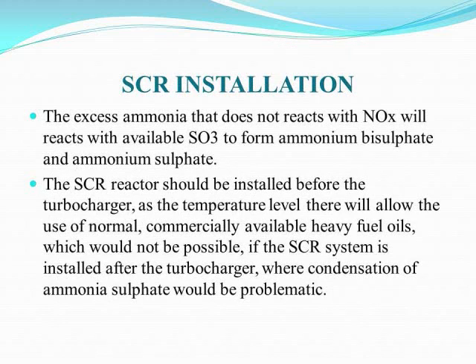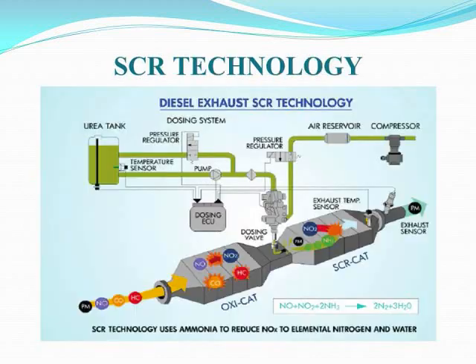A disadvantage of ammonia slip is the formation of ammonium sulfates. A small portion of sulfur dioxide in the flue gas may be oxidized to sulfur trioxide, which then reacts with ammonia at elevated temperatures to form ammonium bisulfate or ammonium sulfate.